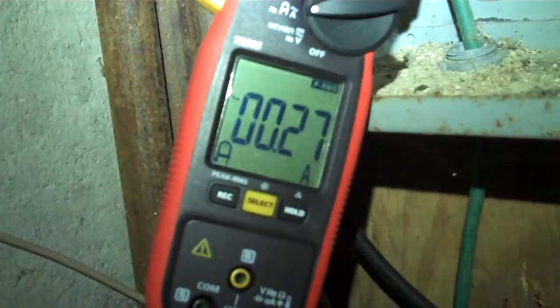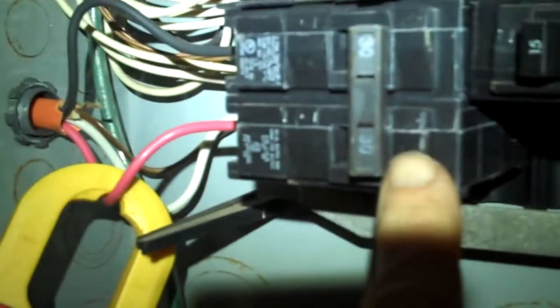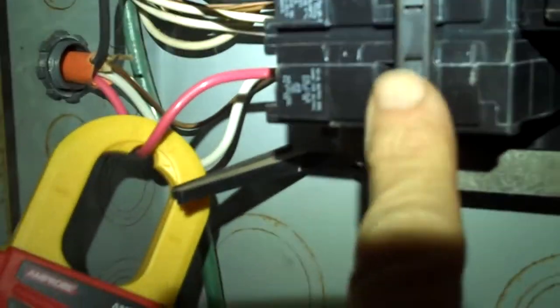Okay, I am going to be measuring the inrush current from my grinder pump, and this is the circuit breaker for my grinder pump. It's a 30 amp double breaker. This is a clamp-on probe that's set up to measure peak RMS, which is going to be the inrush current, and it measures it over an 80 millisecond time period. This is an Amprobe, AMP-310.